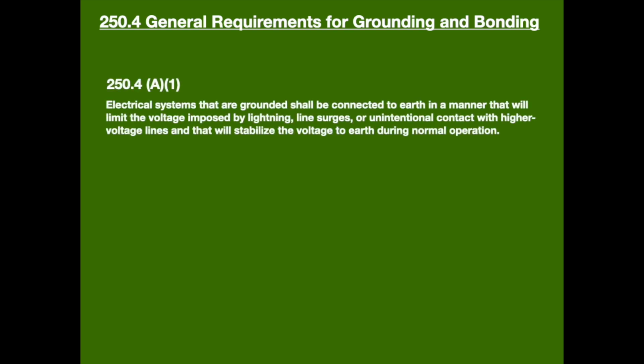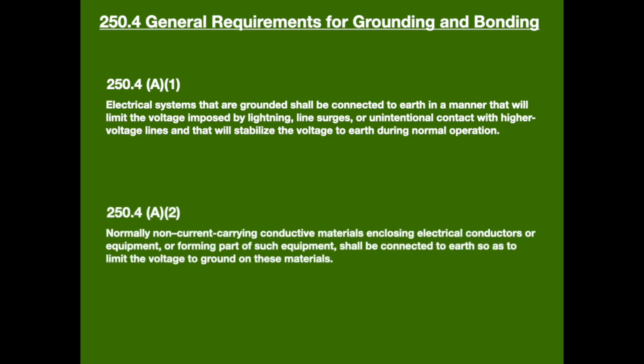General requirements for grounding and bonding. Electrical systems that are grounded shall be connected to earth in a manner that will limit the voltage imposed by lightning, line surges, or unintentional contact with higher voltage lines, and that will stabilize the voltage to earth during normal operation. Normally non-current carrying conductive materials enclosing electrical conductors or equipment or forming part of such equipment shall be connected to earth so as to limit the voltage to ground on these materials.